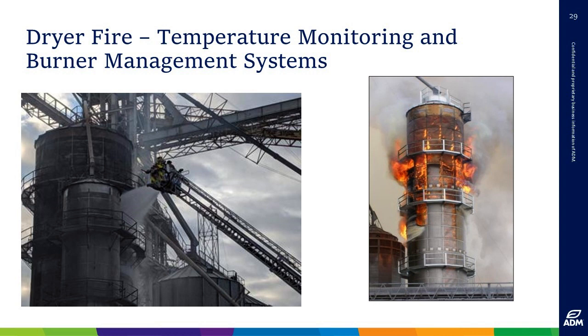Management of change was mentioned. That's kind of an aside, but the circumstances on this was, if we switch from liquefied petroleum to compressed natural gas or liquefied natural gas, we can get you guys a better deal. And we've got this regulator that we can hook up onto your line and it'll work perfectly. And it did. Perfectly burned our grain dryer to the ground. So management of change, outside of CSDs, but also they change it, and now you've got your burner management system set up for one fuel, and it's a different fuel.